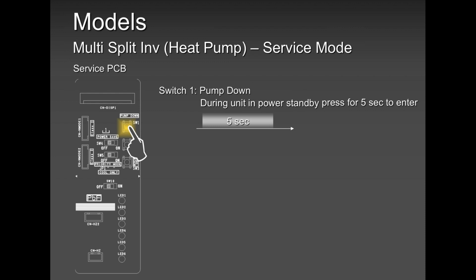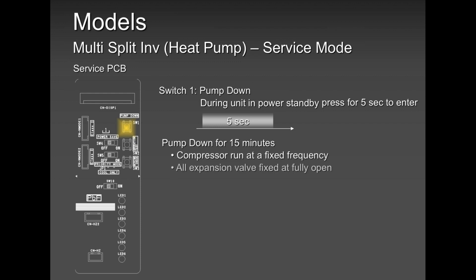Okay? You can pump down the system when you have a problem or when you want to add units. No problem, pump it down. It explains very easily. Push and if you open up the service manual, you will find how to do it. But over here, it's pretty straightforward. All you need to do is close your liquid line, press that for a few seconds, the pump down will begin. You will look at your gauge, the compressor runs at a fixed frequency.